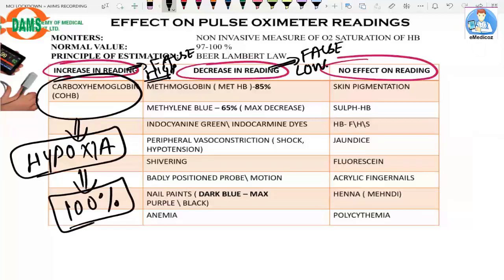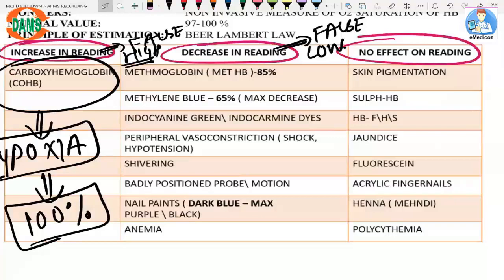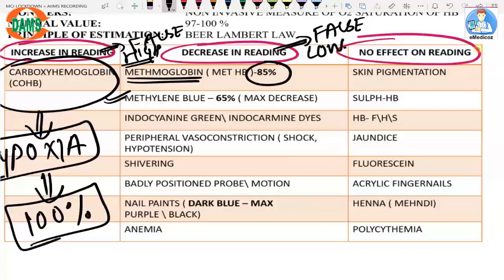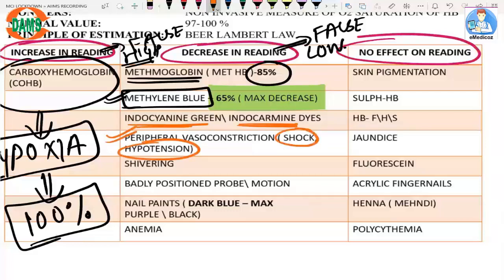A decrease in reading, or falsely low reading, is seen in multiple conditions, most related to decreased peripheral perfusion or use of certain dyes. Methemoglobinemia causes a fixed O2 saturation of 85%. The dye methylene blue causes the maximum decrease, dropping saturation to 65%. Indocyanine green and indocarmine dyes also decrease O2 saturation, as do peripheral vasoconstrictive states like shock and hypotension.